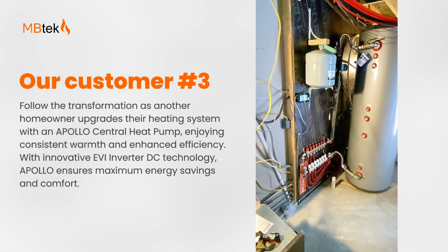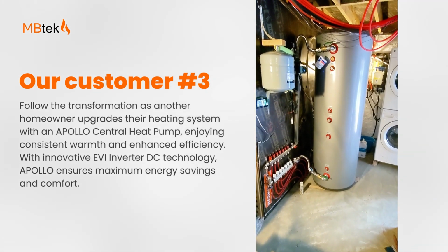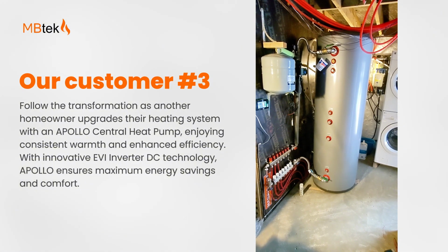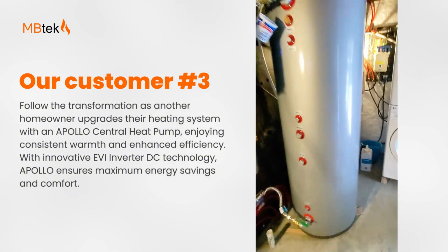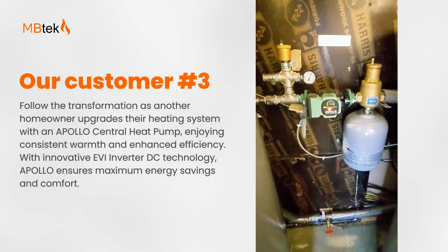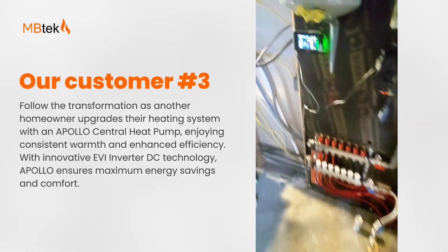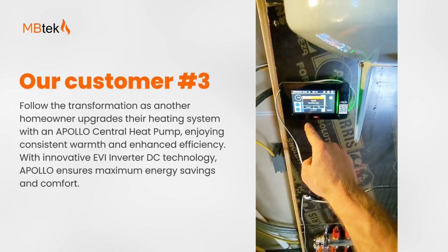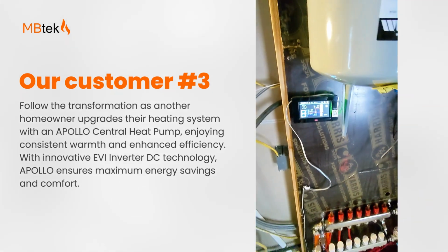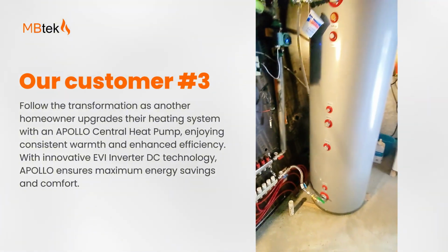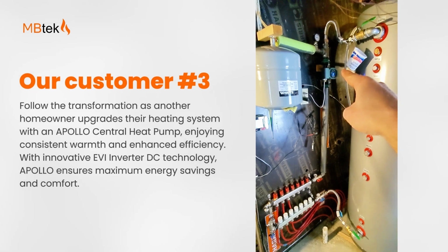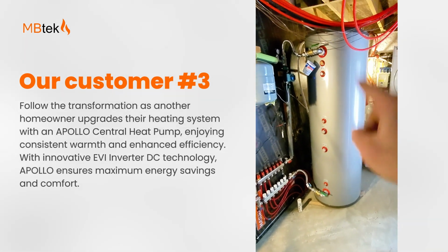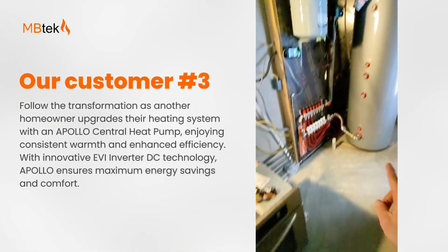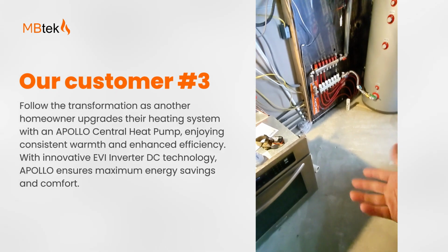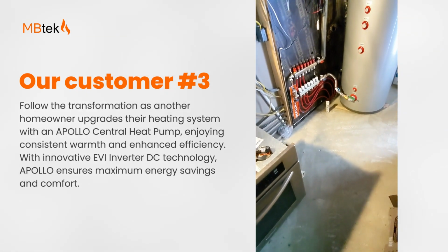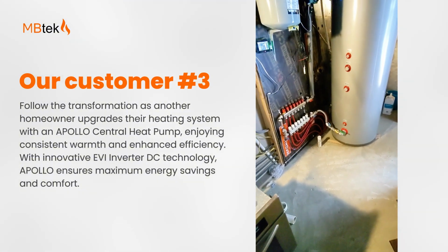I can shut off the heat pump in the evening when the temperature drops in the winter. I'll shut off the heat pump loop, so the circulator pump will stop running, the heat pump will stop running. I can either do it right here from the controller, unit off. Nope, not right now, but yeah, I can shut the unit off, and then I can keep this circulator going and slowly run that hot water through my radiant floor, which the floor itself acts as another thermal battery, because it's, you know, like about, I don't know, 7 tons of concrete or something.